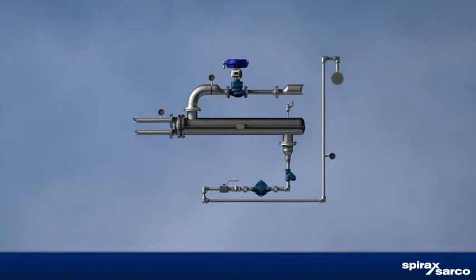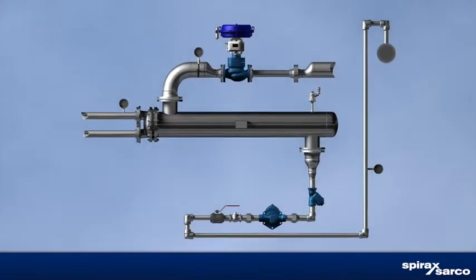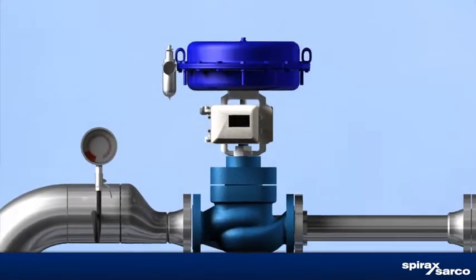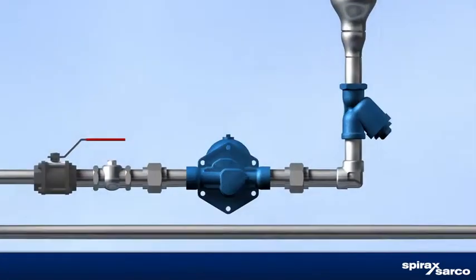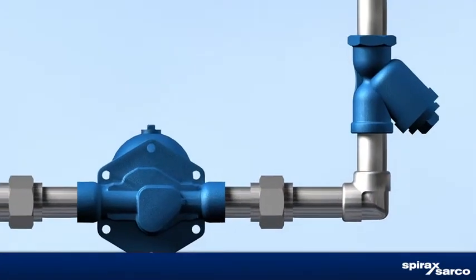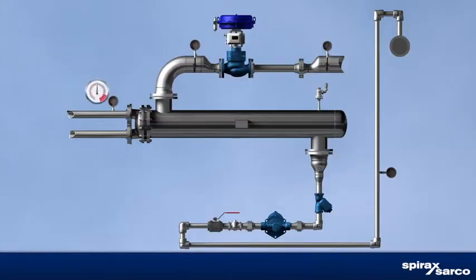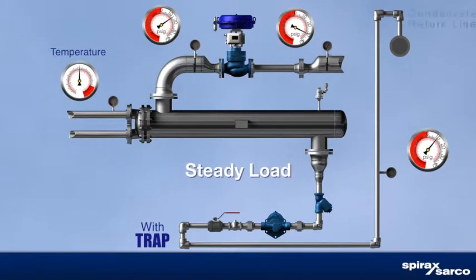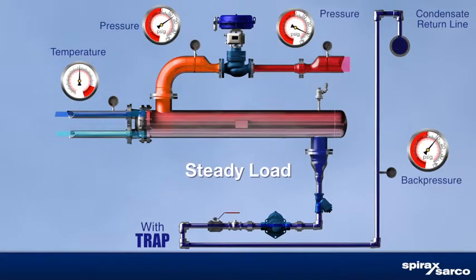The most common process heating heat exchanger hookup involves a temperature control valve on the steam line to the heat exchanger and a steam trap on the condensate line from the heat exchanger. The shell side is a steam space. A control sensor signal at the tube side outlet is used to throttle the steam control valve to maintain set point temperature. Higher pressure in the steam space than in the condensate recovery line produces effective condensate removal and lift to the return system.